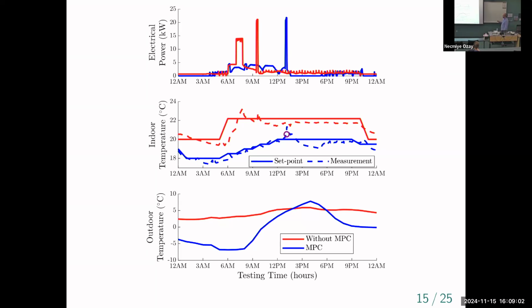And you can see in the indoor temperature profile here, it's lower overnight and higher during the day. And here, I guess it's not really a fair comparison because we're keeping the house somewhat colder, actually an offset of about 2 degrees Celsius or about 4 degrees Fahrenheit, which is pretty significant. So I don't think we want to declare victory based on that indoor temperature difference. But it is worth noting that when we get this step change in the set point, around 6 a.m. we do a step from 20 Celsius up to 22, or about 70 Fahrenheit up to about 74. And when that happens, the low-level controller on the heat pump basically freaks out.